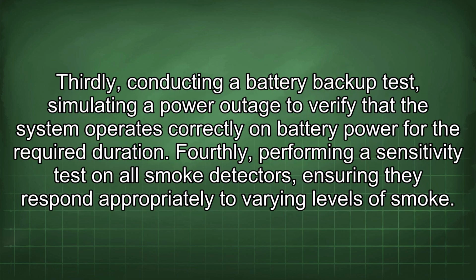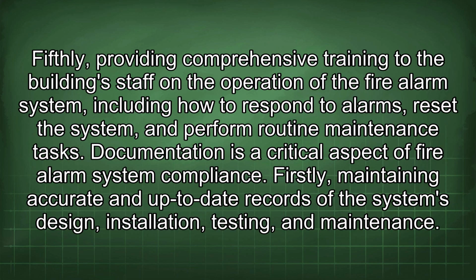Thirdly, conducting a battery backup test, simulating a power outage to verify that the system operates correctly on battery power for the required duration. Fourthly, performing a sensitivity test on all smoke detectors, ensuring they respond appropriately to varying levels of smoke. Fifthly, providing comprehensive training to the building staff on the operation of the fire alarm system, including how to respond to alarms, reset the system, and perform routine maintenance tasks.